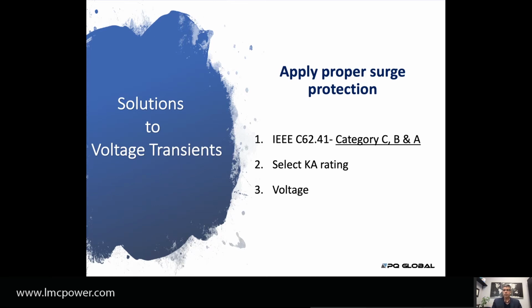All we have to do is look at three simple steps to figure out how to solve this problem, referring back to IEEE C62.41. They give us three categories. Category C is a surge protector designed to be installed at the input of a building. Category B is a surge protector designed to work within the building. Category A is a surge protector designed to be connected directly to the equipment you want to protect.